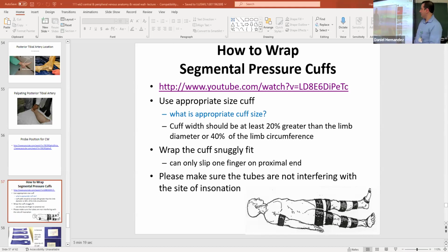Hi, my name is Rob Daigle. I'd like to demonstrate a technique for wrapping blood pressure cuffs, particularly with these cuffs that tend to be sort of uniform for physiologic testing systems. This is a portion of the blood pressure cuff. It contains the bladder. This has the hose coming out. So this is the part that we're going to put towards the skin. The other part of the cuff right here is just essentially the wrap containing the Velcro.